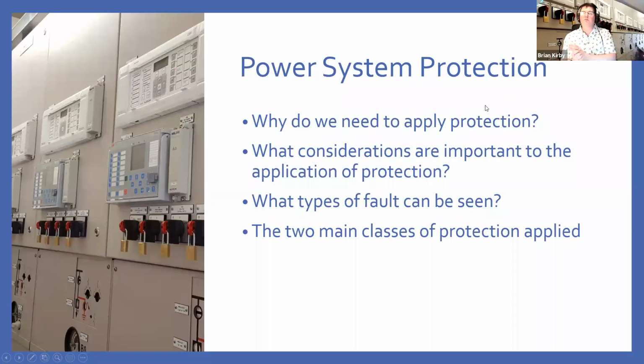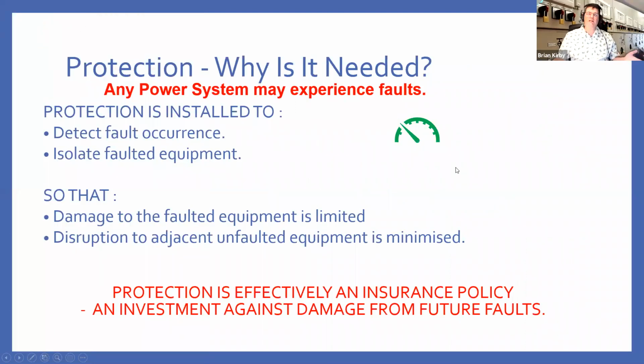So power system protection, why do we need it? And what do we need to consider when we're applying it? What type of fault are we going to see? And what classifications of protection are we considering? So why do we need protection? Well, protection is effectively an insurance policy. Any system, no matter how well designed, may have a fault occur. And if you want to protect it, you need to detect that fault and isolate it to limit the fault and to limit any disruption to any adjacent equipment.